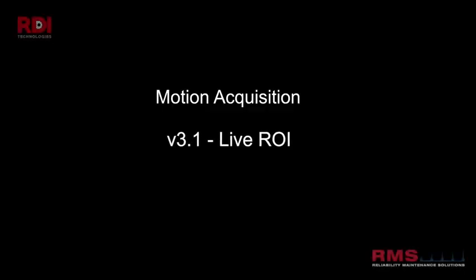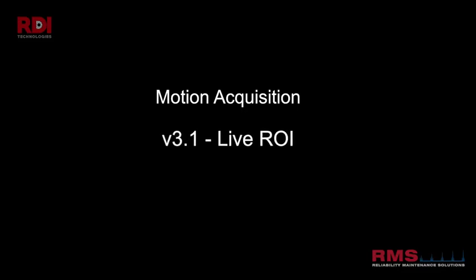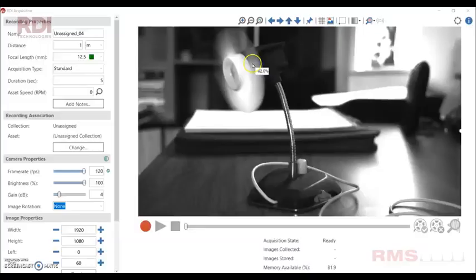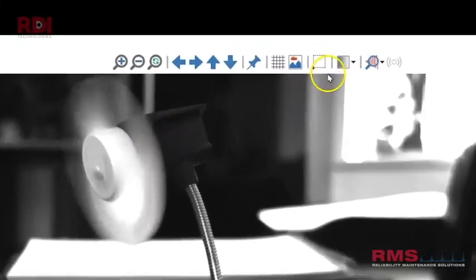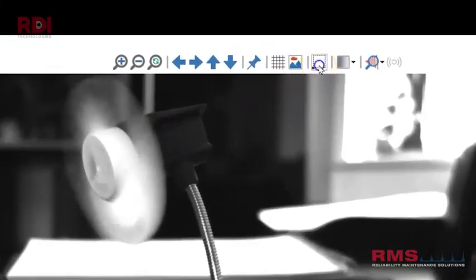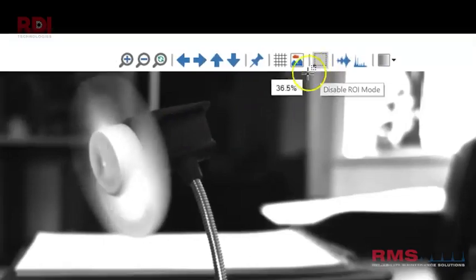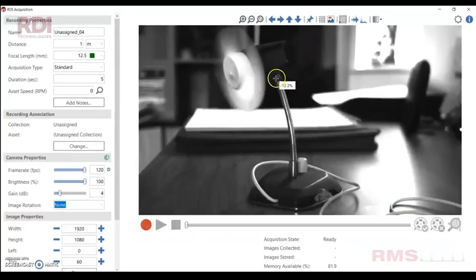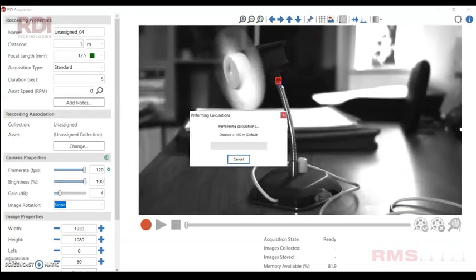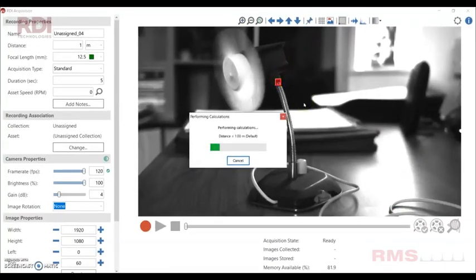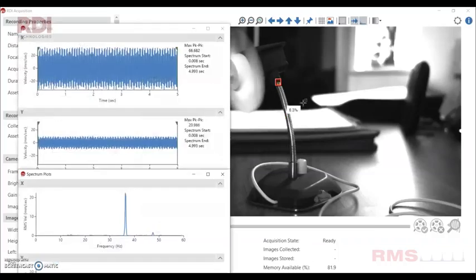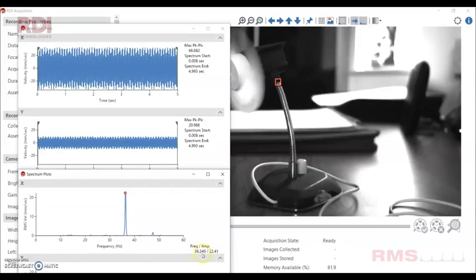Machine startup. This is a fan going through a resonance problem as it increases in speed. And then we can do detailed analysis afterwards. Really fantastic tool. Live region of interest. So this is where we can actually do a measurement in the live mode. This is really useful just to get a feeling of the different frequencies on the machine before we actually start saving recordings. We get waveform frequency data. We can look at the amplitude. Really useful tool that.